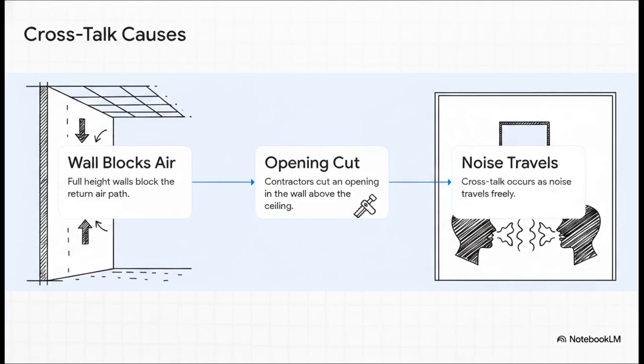But here's where it gets kind of funny, and it brilliantly illustrates what happens when building designs get a little complicated. Sometimes offices have full-height walls that go way past the drop ceiling, all the way up to the actual roof deck. That completely blocks the return air path. So to fix the airflow, contractors will often cut an opening in that wall above the ceiling. But by doing that, they accidentally create a perfect little tunnel for noise to travel freely from one side of the wall to the other.